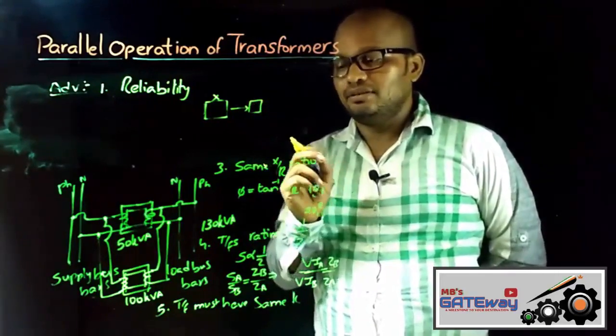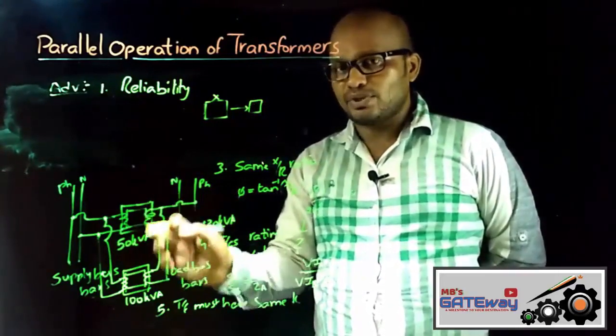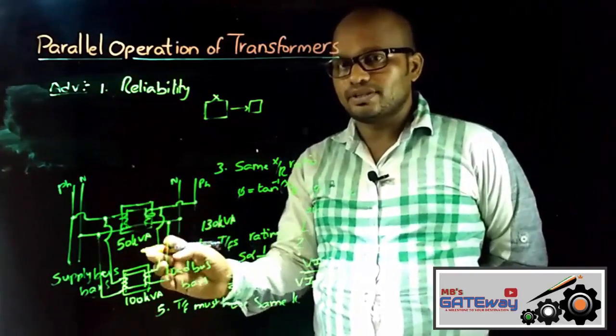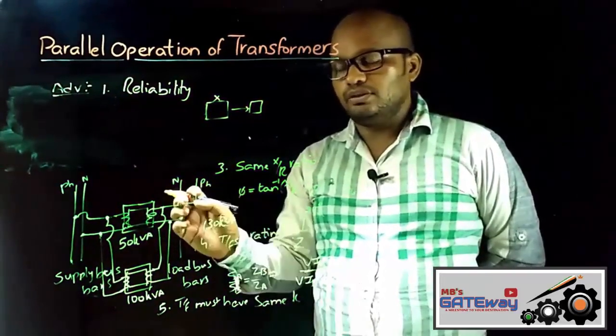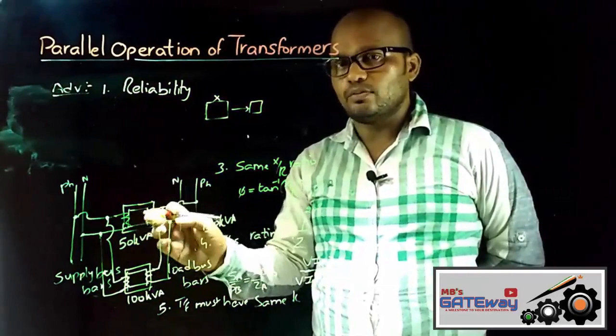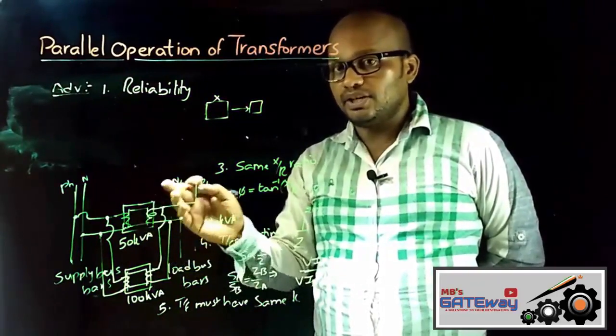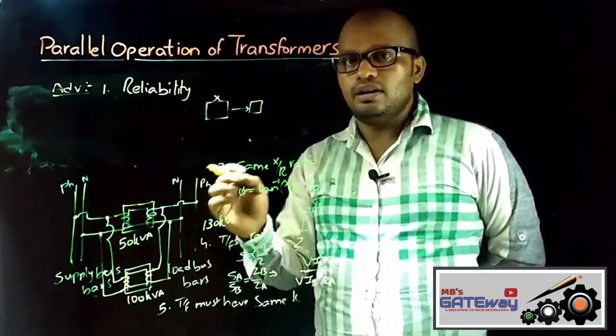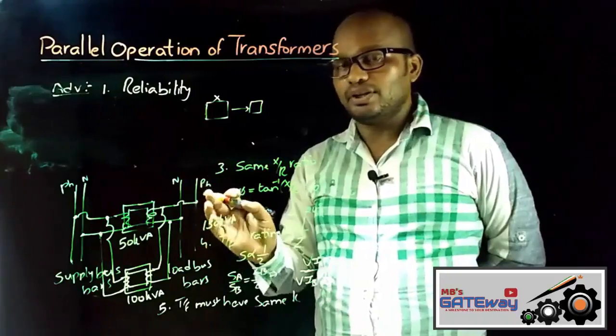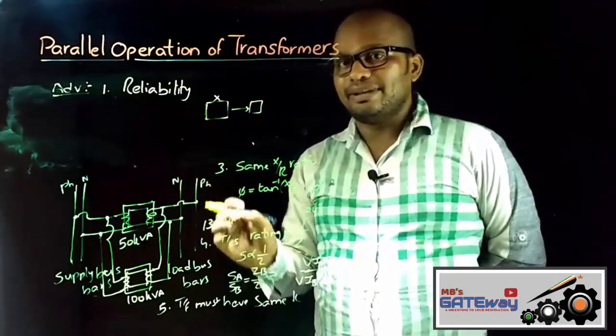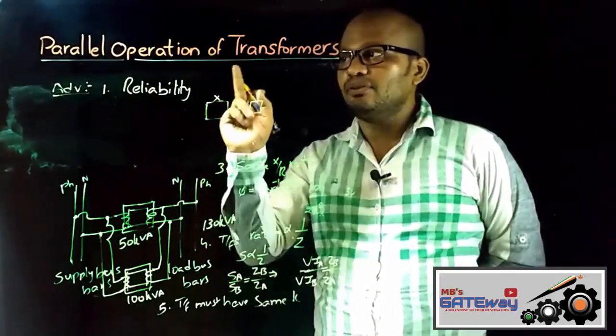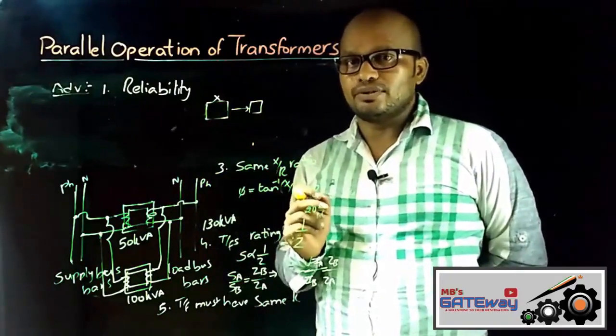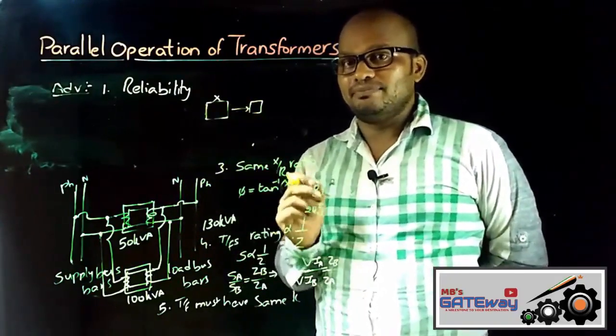And coming to parallel operation of transformers, if these two transformers are supplying power to the load, and due to some unknown reason one of the transformers fails, then continuous supply can be maintained through the other transformer. So the important criterion, continuous supply, can be maintained in case of parallel operation of transformers. That is why reliability is more.